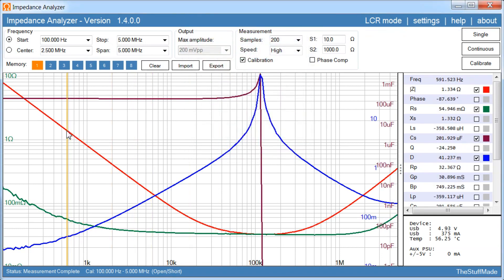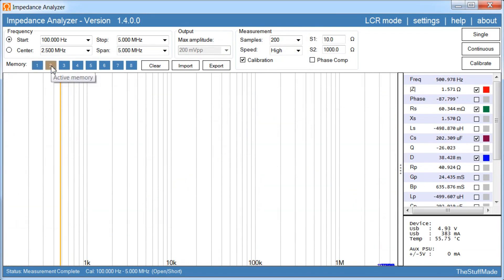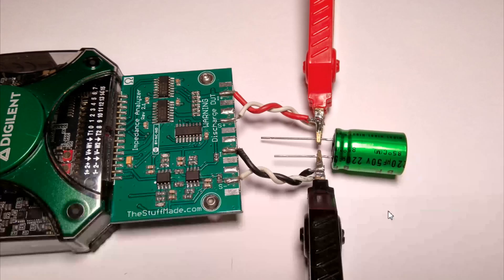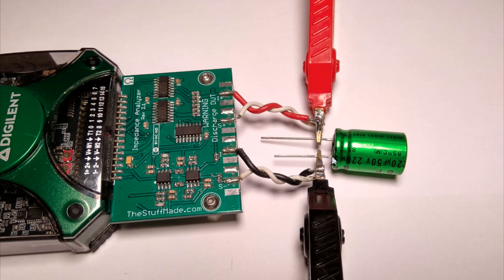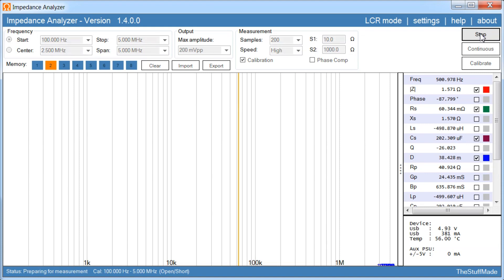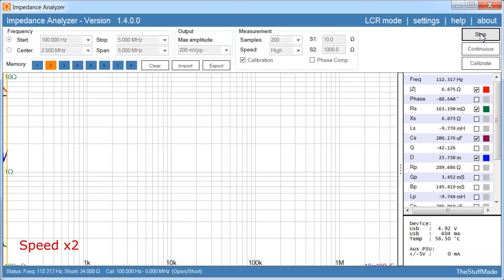Now I'll try to do a second measurement, and I'll select the second memory slot up here. This time I've moved the Kelvin clips just a few millimeters away from the body of the capacitor here. And then let's repeat the measurement. And here we go.